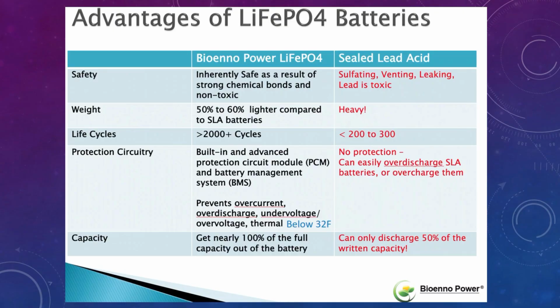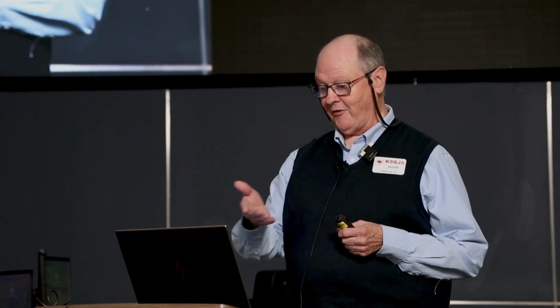Every lithium iron phosphate battery, whether Bioenno or another manufacturer's, has a little circuit board built into it. That circuit board, sometimes called a battery management system or a protection circuit module, provides additional protections including overcurrent, over discharge, under voltage, and over voltage protection. Lithium iron phosphate batteries should not be charged below 32 degrees Fahrenheit, and a good battery protection circuit also includes a temperature transducer to determine what the battery temperature is. Remember, I referenced some YouTube videos you can look at for evaluations - there are lithium iron phosphate batteries on the market which, while they have a battery protection circuit built in, don't have the transducer to test for temperature.